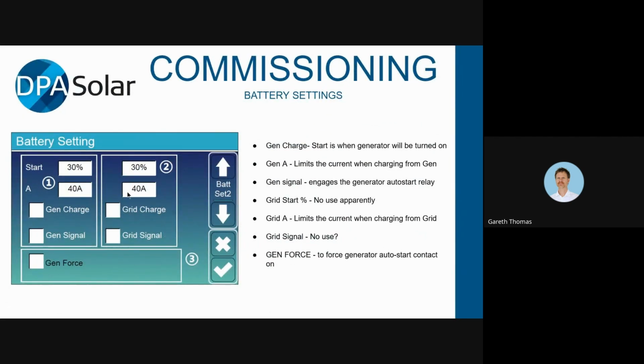And you've got some settings here, which I find slightly confusing to begin with. On the left-hand side, you've got the gen charge settings, and on the right-hand side, you've got the grid charge settings. So the gen charge setting, the start value, that's the percentage that the battery will need to be for the generator to turn on.